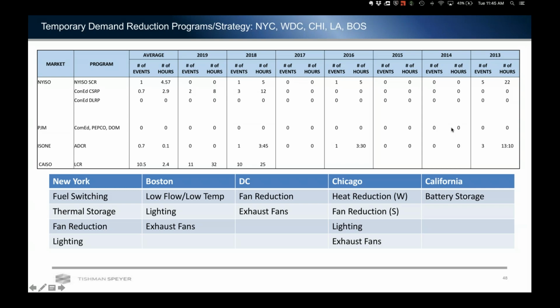Because we have spare capacity in our central plant and our chilling equipment, we employ some low flow, low temp strategies where we reduce the supply temperatures coming out of our central plants and going to our air handling units. Discharging colder water into the air handling units is ultimately going to reduce our pumping efforts and flow requirements. So keeping the same tonnage, but burdening the chillers a little bit more with their ability to cool that water, is how we participate specifically in the New England marketplace because of the steam-driven machines there.